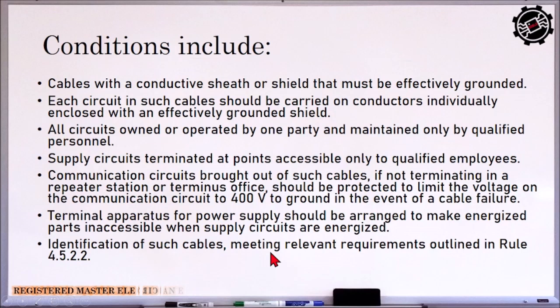So direct buried cable and cable in duct not part of a conduit system. So meaning ito yung mga cable na they are not part of a conduit system, no? So they are directly buried cable or nasa talaga sa ating ducting. Okay. So this article is applicable to direct buried cables. So supply cables operating above 600 volts to ground must have continuous metallic sheath or concentric neutral that is effectively grounded. Splices or joints in the metal shield, sheath, or neutral path must be made continuous but need not be concentric. Cables of the same supply circuit may be buried with no deliberate separation.